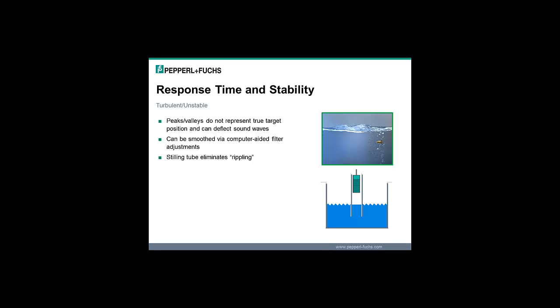And also, sometimes even without software, there are some methods to smooth out instabilities, and one is a stilling tube, where you can put the sensor inside a tube, and you can see that graphic on the bottom right. It's kind of like a nice tranquil little island inside the tube. Because there's no waves in there, the waves are on the outside, but the tube kind of stills everything. So stilling tubes are one method to get rid of widely deviating or fluctuating outputs due to an agitated surface.